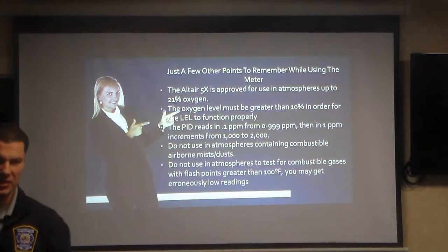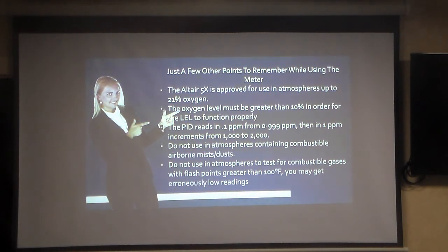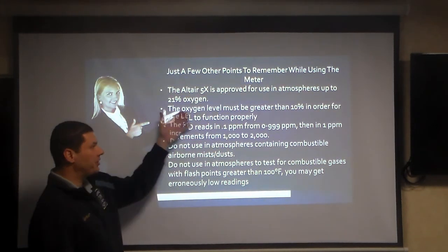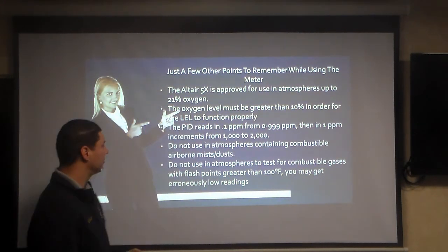I usually tell people if the oxygen sensor is not within the normal range, do not use it, do not enter, unless there's a life safety hazard. For our purposes, there really is no point to enter an atmosphere that's oxygen deficient. But remember, if it's not greater than 10%, the LEL will not work.